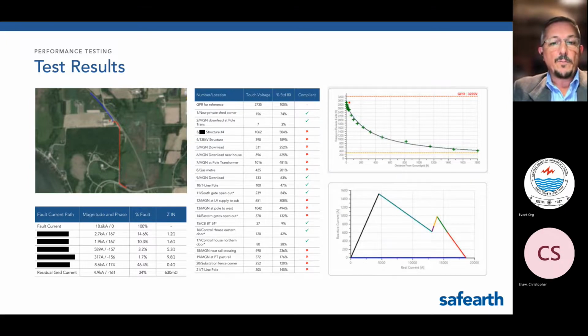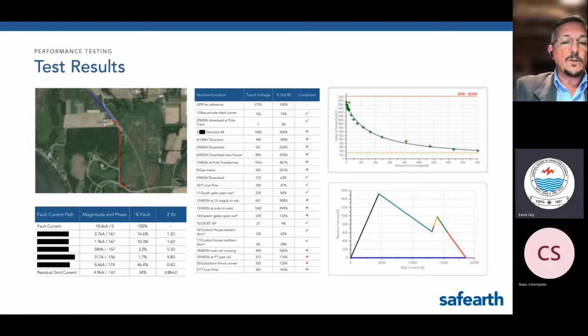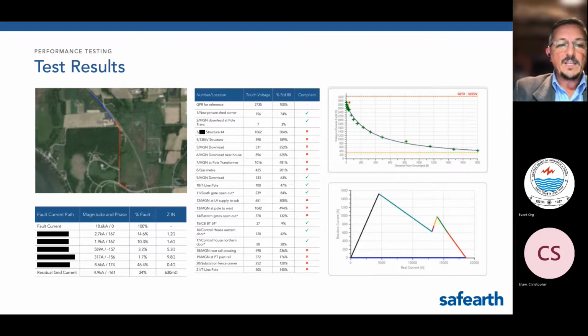If you look at the graph in the bottom right, the blue line at the bottom is a vector of the injected current for the fault, and the various colours climbing back up to the top left are current splits that have been measured, including their phase angle. The black vector is the residual current, which was passing into the soil through the grid. So how do we measure current splits with phase when we're up the top of a transmission line measuring a shield wire, or when we're in a cable pit on a screen, or when we're on a neutral?